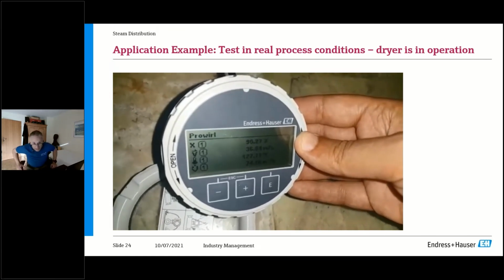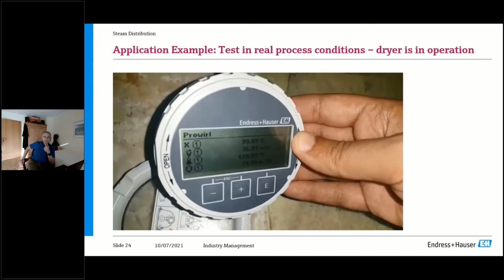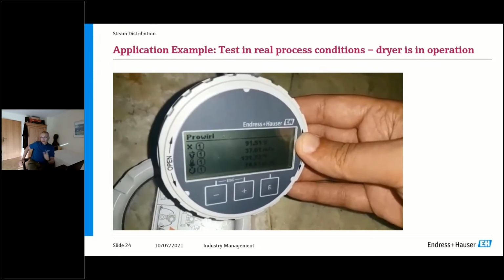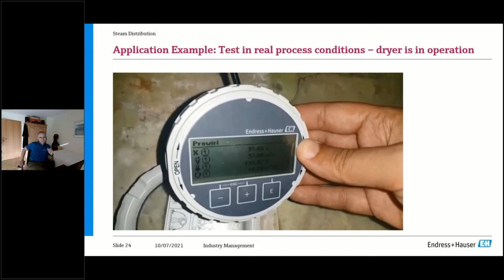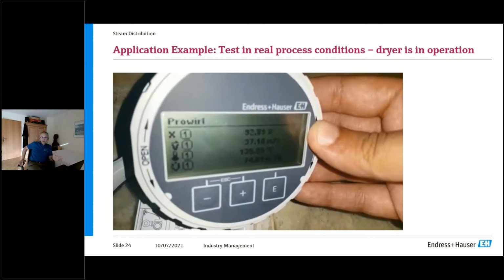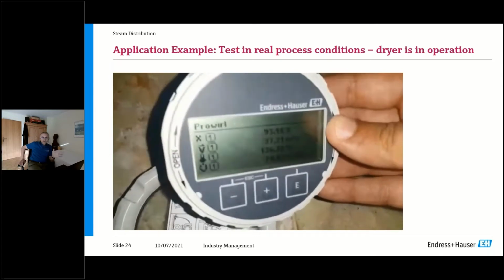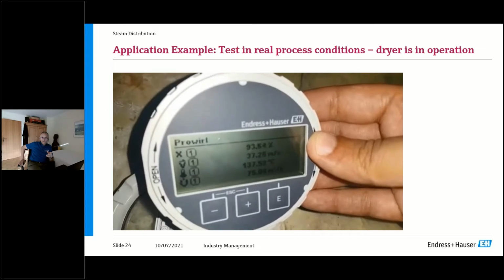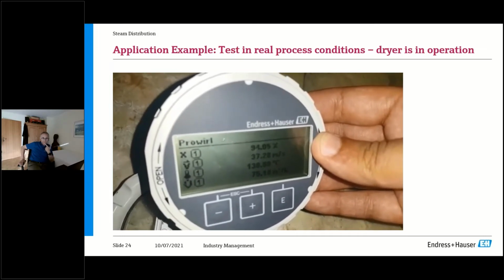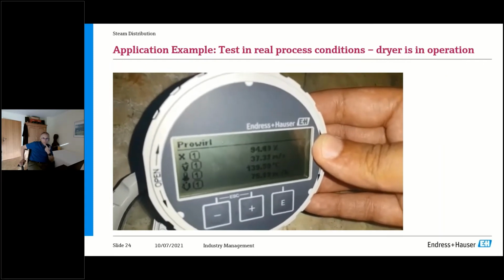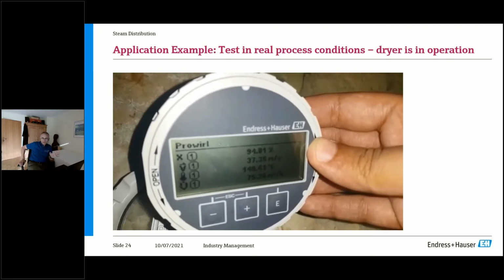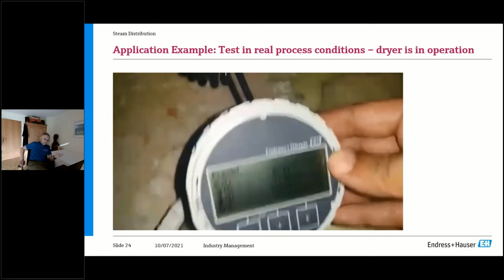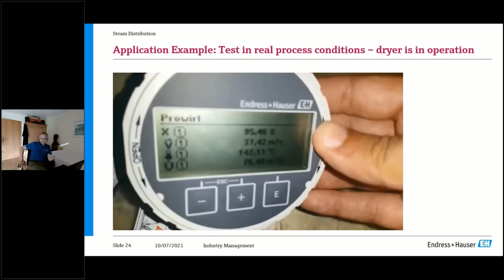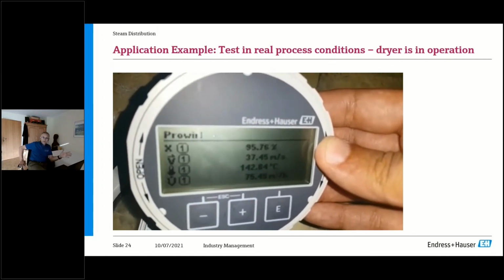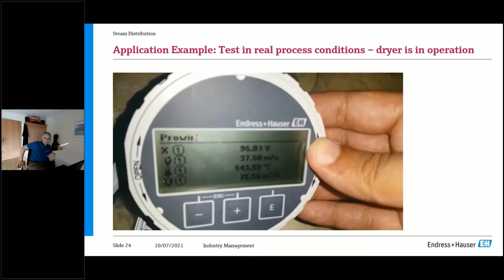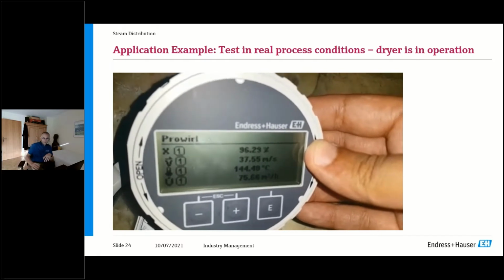Here you see an application example. Here we have a vortex meter of ours downstream of a dryer and a pressure reduction. And the dryer here, in this case, can be switched on and off, an interesting one. Here you see that typically the steam dryness fraction of the main line is 90%-ish. And when you switch on the dryer, you see the dryness fraction increase from 90% up to close to 100%. You can also see the amount of information you can assign to the display. You can assign the dryness fraction, the degrees of superheat, here they have the velocity. You can assign energy in megajoules or MMBTUs, or mass in tons per hour, totalizers, whatever you like. So plenty of information is available from that device.